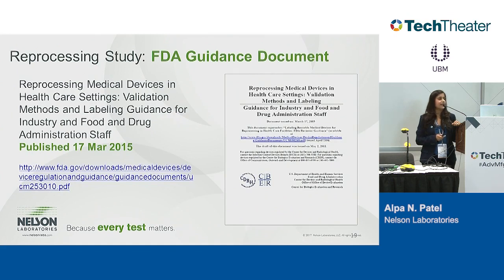This is one of the FDA guidance documents that, if you're interested in reprocessing or are doing reusable medical devices, is a very important document to be familiar with. All the validation plans, what they need in the validation, and what should be validated are all in this document. And they specify very clearly what kind of controls they want in place for the validations as well.